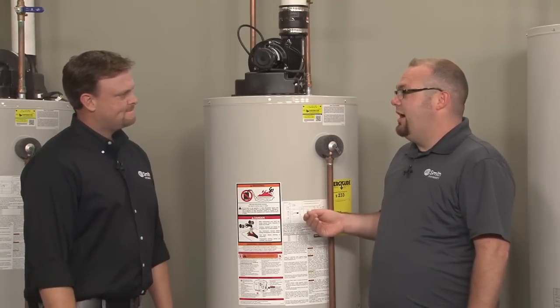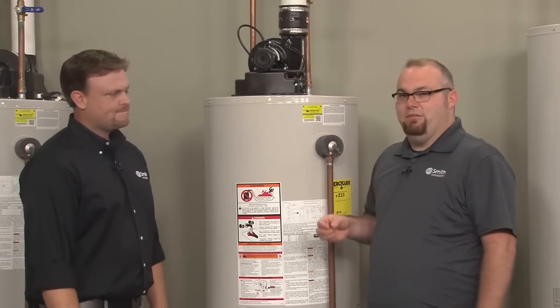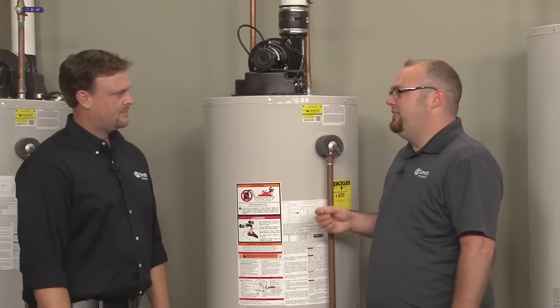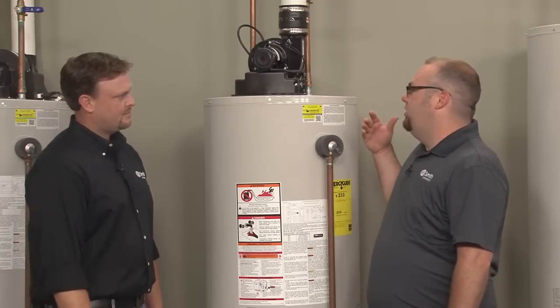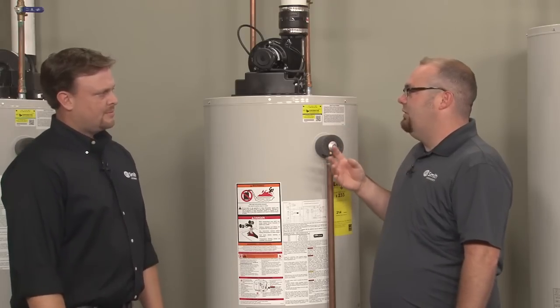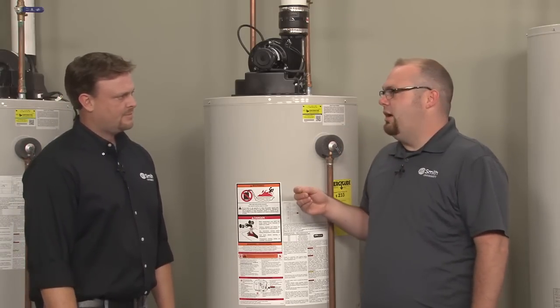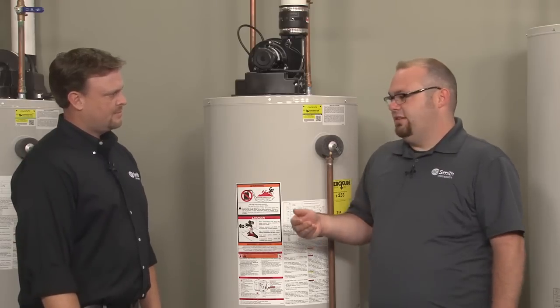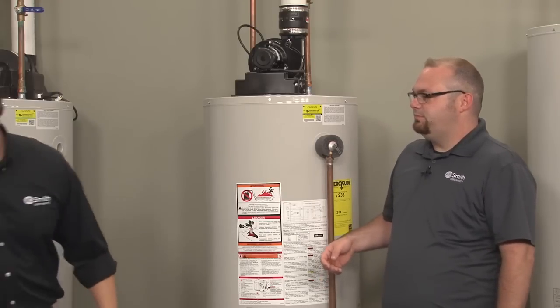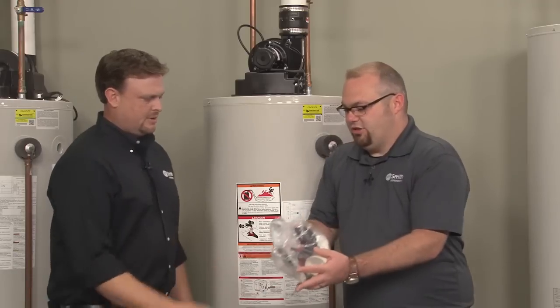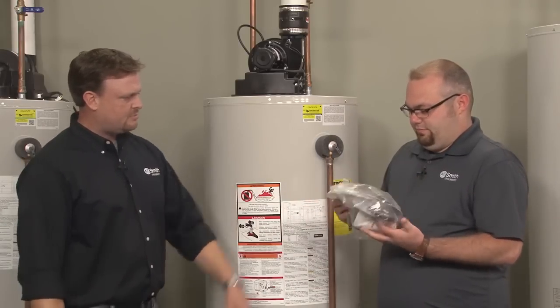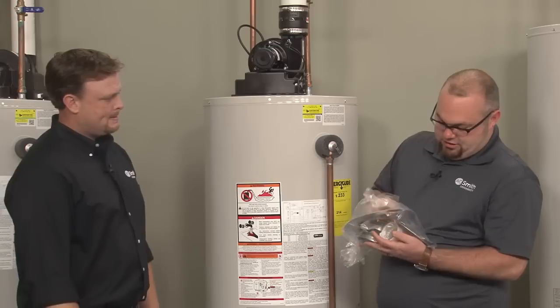And one of the reasons why is because every power vent's different. The venting specs are not the same on every single one. And so a newer power vent, especially this one, the venting requirements are a little bit different than an old power vent. And one of the other differences, I think you actually have them. Yeah, some terminations here. It's termination screens. That bag actually comes with the water heater. Yes, the bag comes attached to the heater.